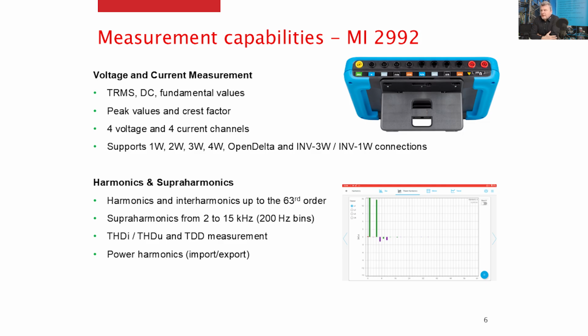Regarding THD and TDD, total demand distortion, we support total harmonic distortion for current and voltage, and total demand distortion for the measurement. For total demand distortion, the nominal current of the current clamps is used as load current, so we need to recalculate later to the maximum current achieved during the measurement. You need to do this with the MP-Vision software. We also implemented bar presentation of power harmonics. So at each moment, you can monitor which harmonics are generated and which harmonics are absorbed from the network. This is simply visible in the Power Harmonics bar graph.